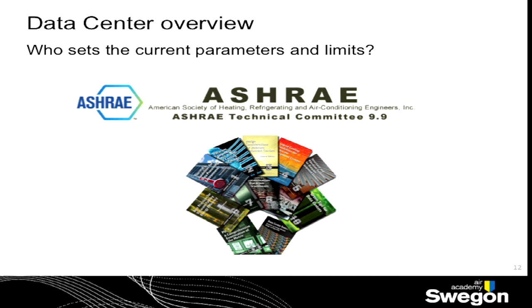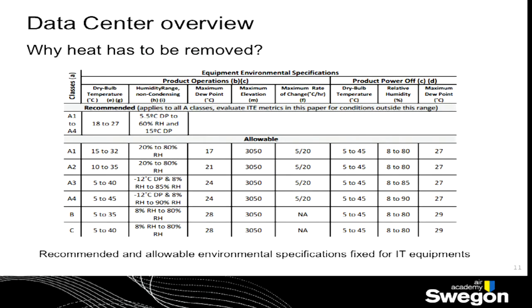And if we want to build, if we want to manage a data center, the only thing we have to do is refer to the ASHRAE rulings. There's nothing else. It's always up to the ASHRAE. It sets the temperatures for the A1 to A4 classification for fixtures in the data centers. Okay, so it sets not only the temperature conditions, but the humidity conditions too. Of course, it sets a recommended situation, so from 18 to 27 degrees, and an allowable situation. So now we are going deeply into the definition of what recommended and allowable mean.